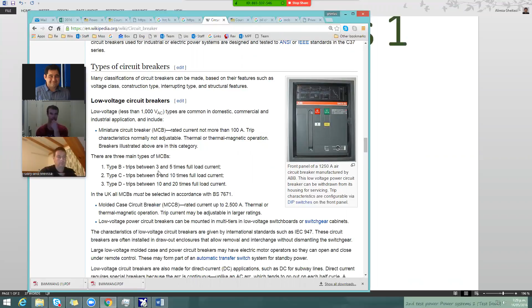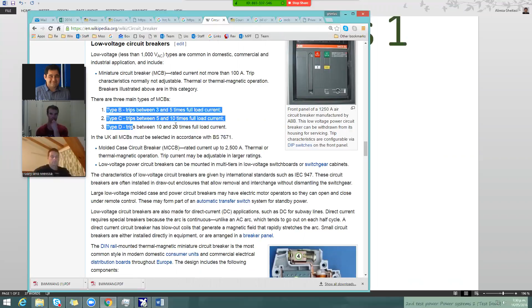As you can see, we have different types, and this MCB is not adjustable. Once you want to select that based on British standard 7671, you need to make sure you're using the right type. In New Zealand, mostly people use type C, but sometimes you may need to use other types. I'll leave you guys to read these things yourself.